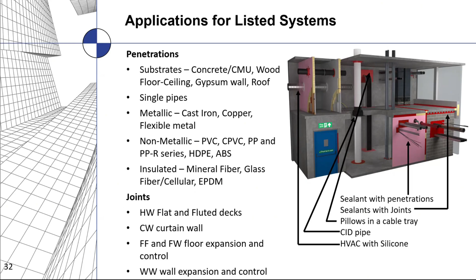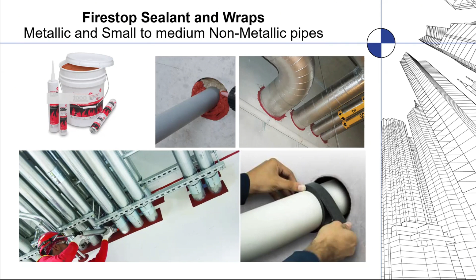In the case of metallic and small to medium-sized non-metallic pipe penetrations — like PVC or CPVC sprinkler pipes, or other kinds of pipe, Aquatherm high-pressure water lines, or duct work going through these openings — usually some type of sealant or wrap is used to fill those openings. Sealants by themselves will handle some smaller plastics and large metal pipe, but when you need a large plastic pipe, they move toward wrap-type materials, a pre-cured intumescent strip that acts like the material you saw burning in that electrical box.